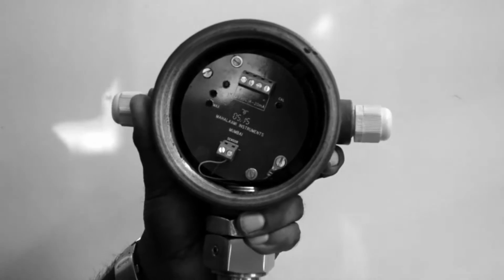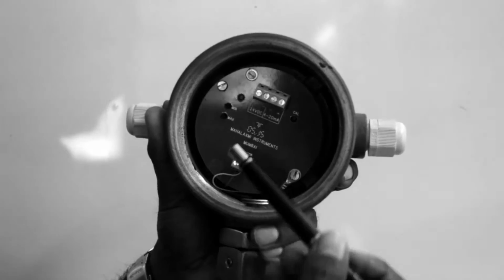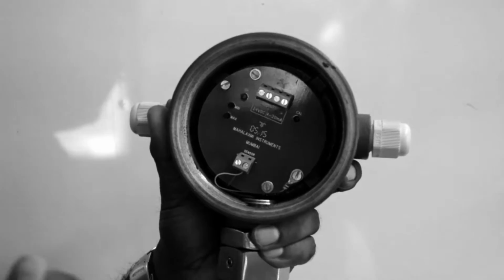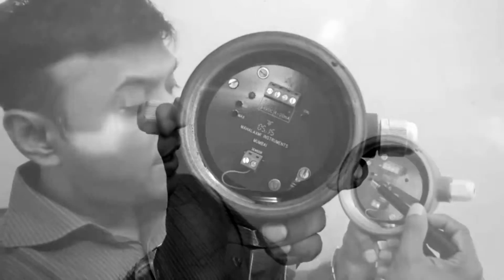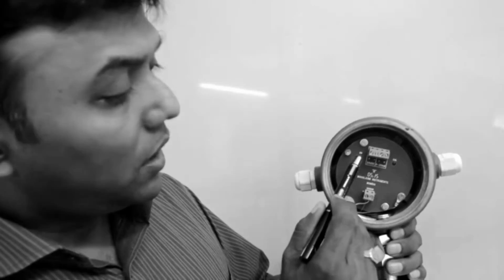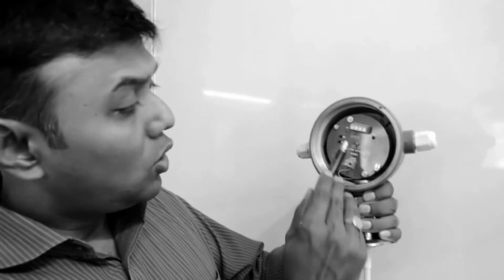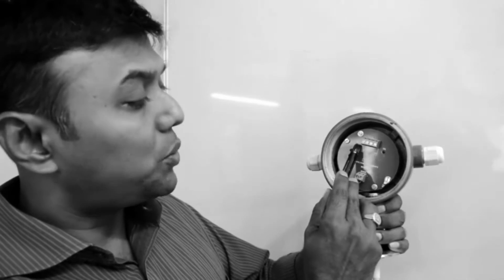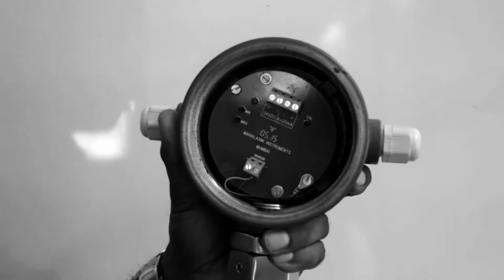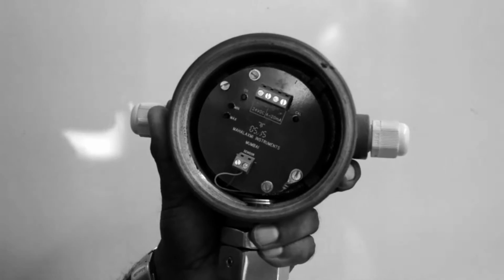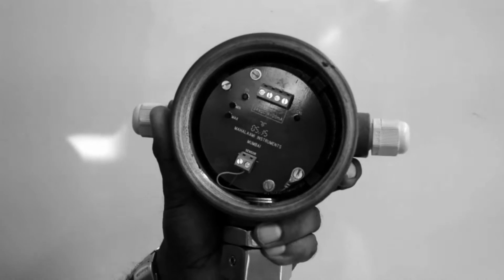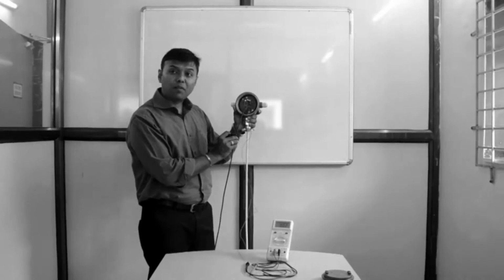So this is a 3-wire capacitance level transmitter, and then you have 2 push buttons for calibration, the minimum and the maximum. And then you have the 2 LEDs, the power supply. When you give the power supply, you have the left on LED which will glow. On the right you have the calibration LED. So when your instrument goes into a calibration process, you have the red LED glowing. We shall now connect the instrument, give it the power supply, and tell you how to go ahead with the calibration process. We have connected the power supply cord.